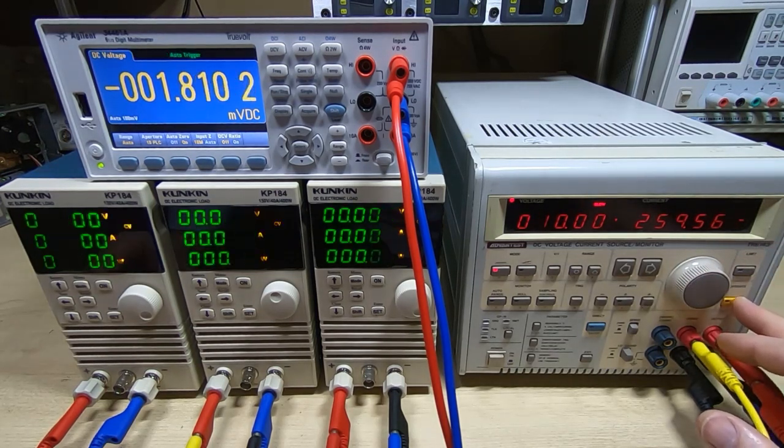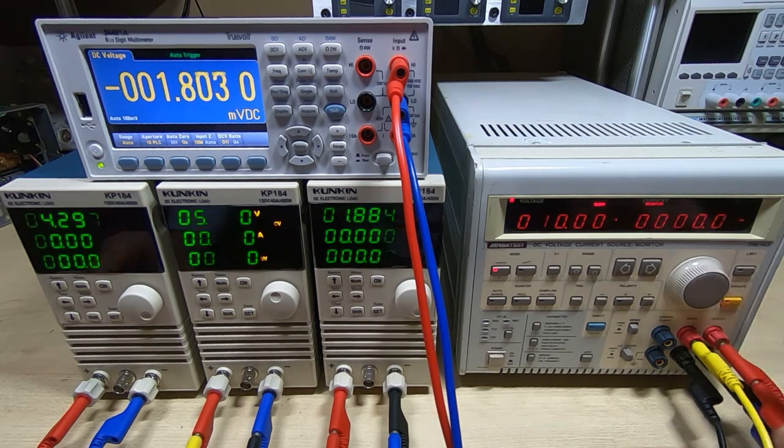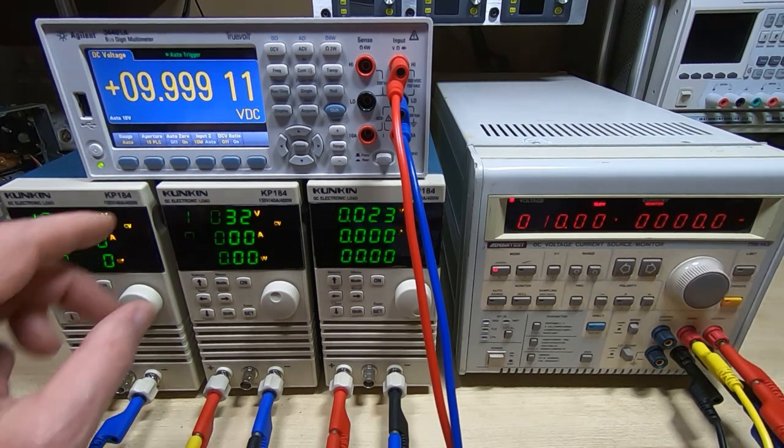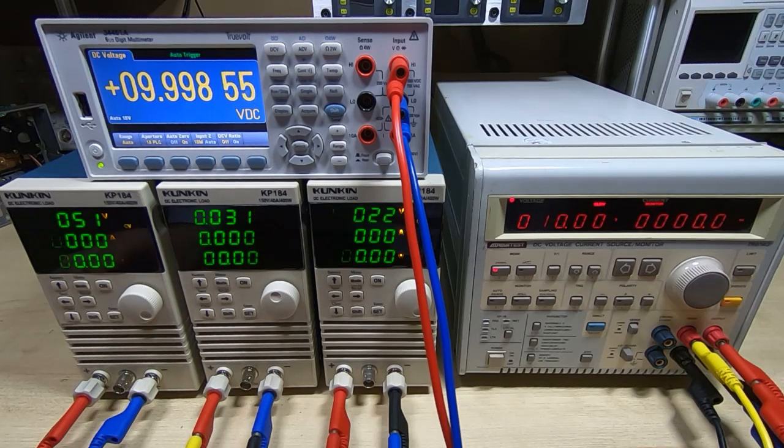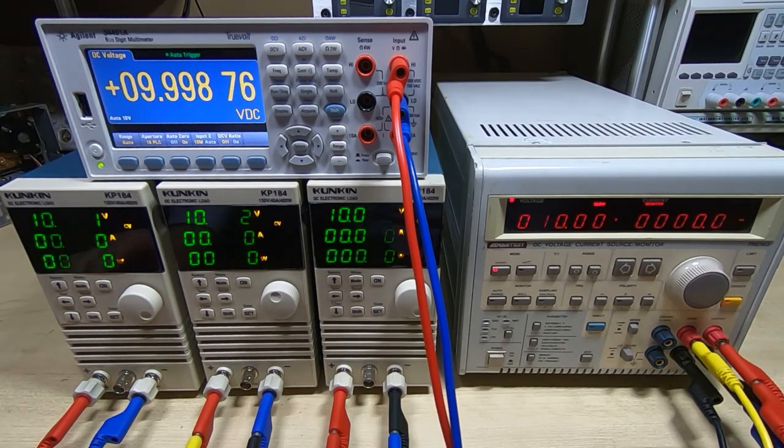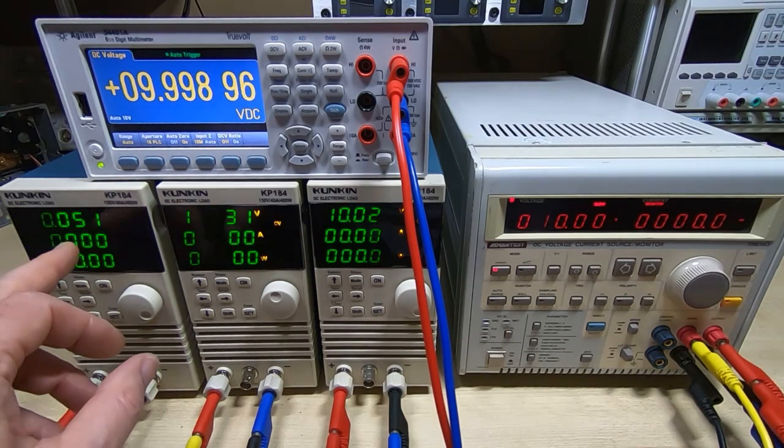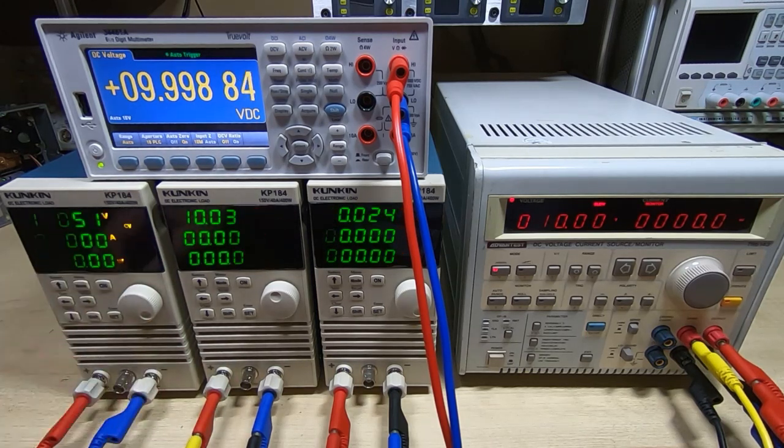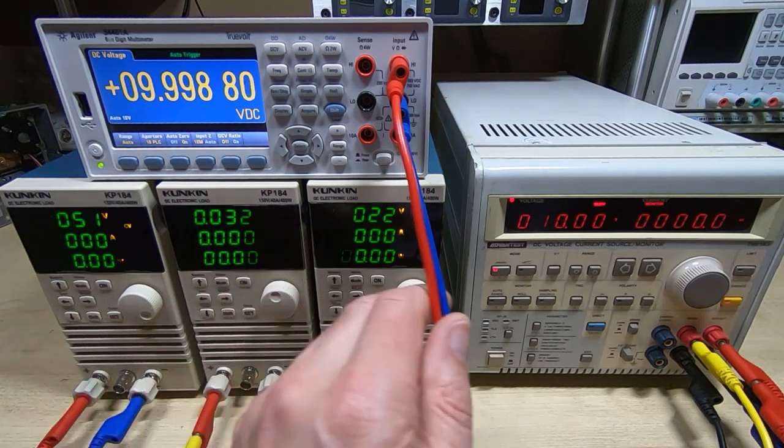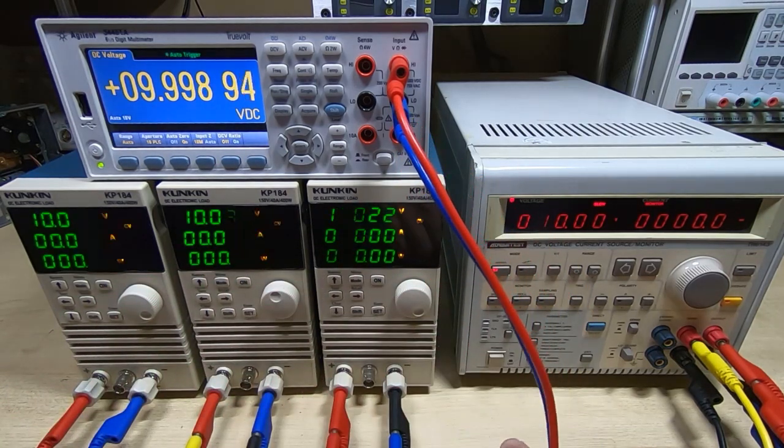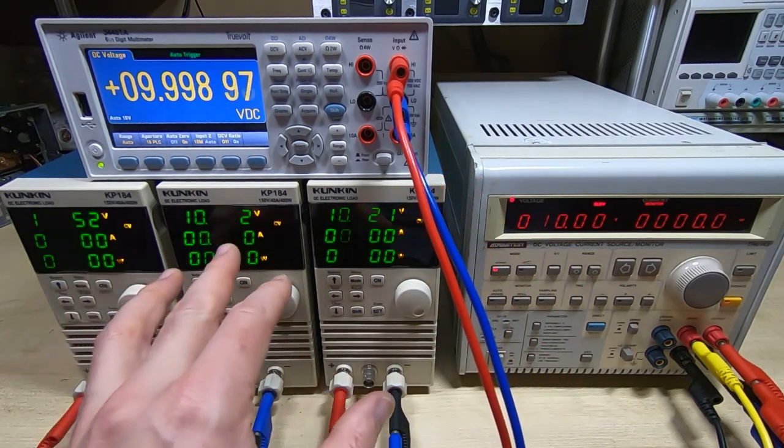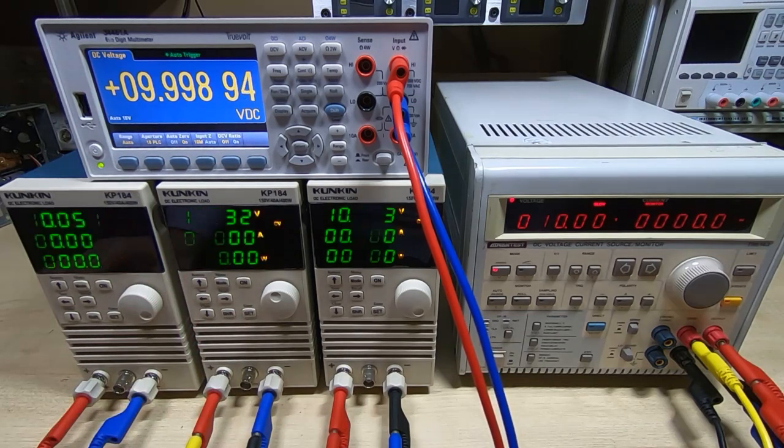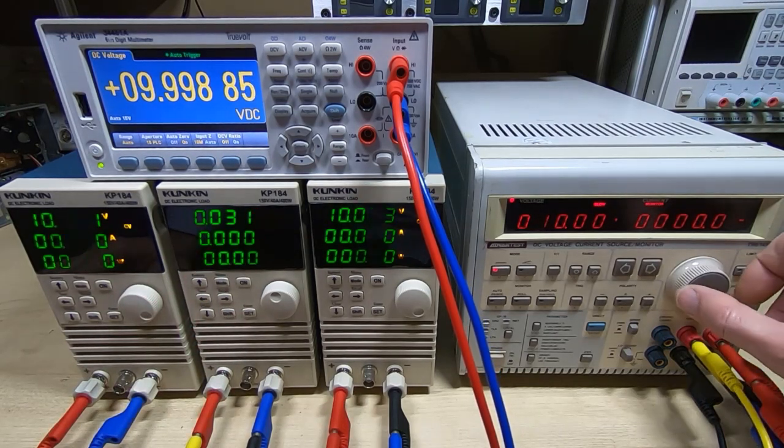I'll turn the output of the source on and we can now see that we're getting very close to 10 volts on the Agilent. But if we look at the KP184s we'll see they're not too bad but we're getting 10.051, 10.032, and 10.023. It's not terrible but it would be nice to have them a bit closer.